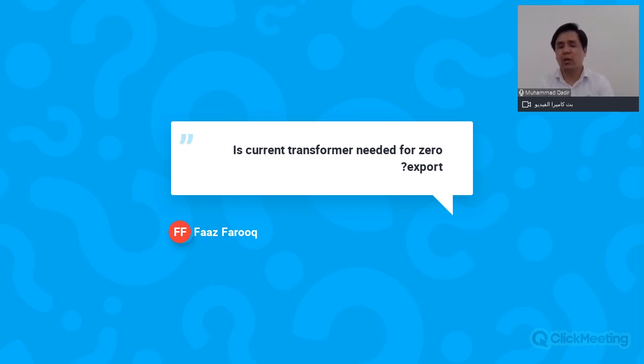Why is that? Because the current transformer is actually measuring the amount of current that is being taken from the grid or the amount of current that is going towards the grid. In order to calculate how much power that is equivalent to, the voltage is also measured from the point of connection through the cables that you are connecting. The multiplication of the current and voltage is a power value which is being read by the smart logger, which accordingly reacts if a control is required.